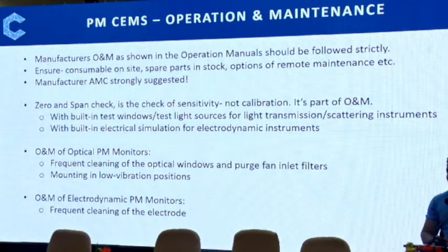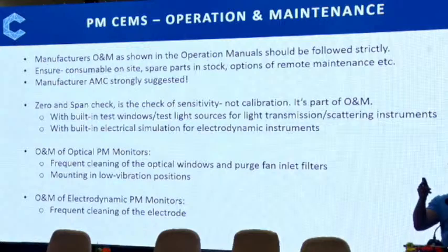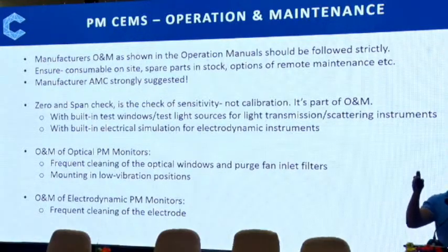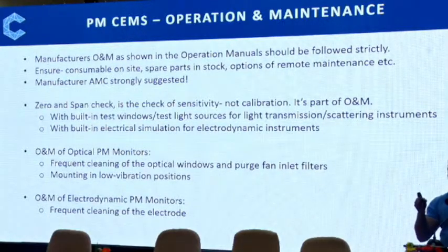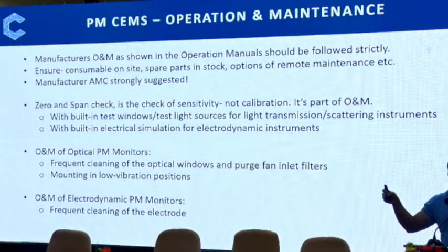For PM monitors, you can use the built-in test window and test light sources for light transmission and scattering instruments. You can do zero and span using electrical simulation in the case of electrodynamic equipment. In the operation and maintenance of optical PM monitors, frequent cleaning is required. It also depends upon your experience and the dust concentration in your stack. You know how often your lens gets covered or needs cleaning. It is not fixed that it will take 15 days or 20 days. It is also your experience in your plant, how frequently you have to do it. So you need to develop your own.